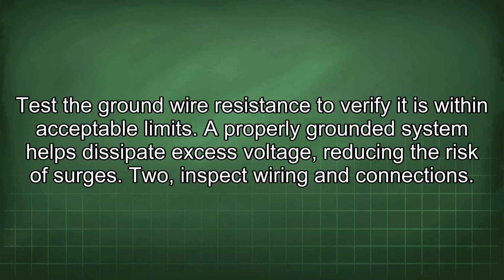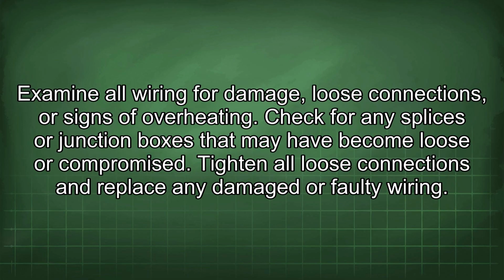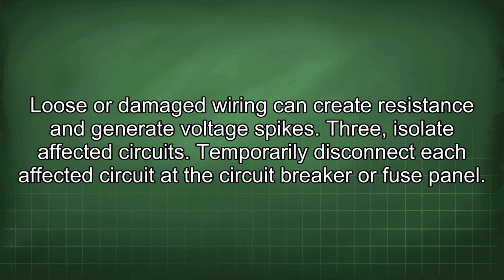2. Inspect wiring and connections. Examine all wiring for damage, loose connections, or signs of overheating. Check for any splices or junction boxes that may have become loose or compromised. Tighten all loose connections and replace any damaged or faulty wiring. Loose or damaged wiring can create resistance and generate voltage spikes.